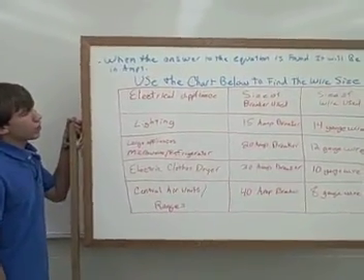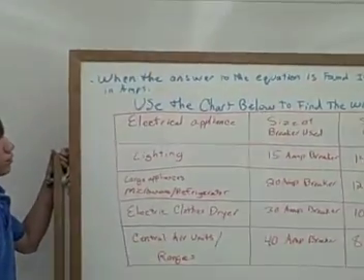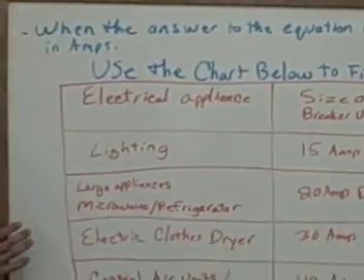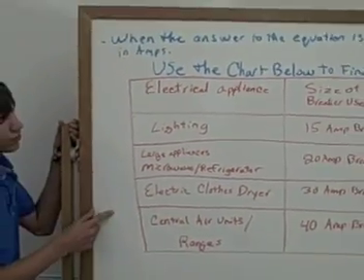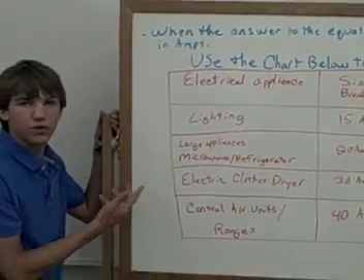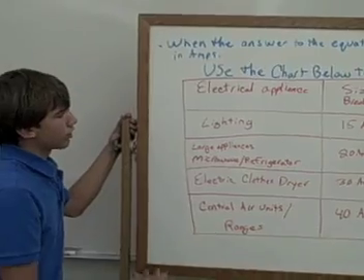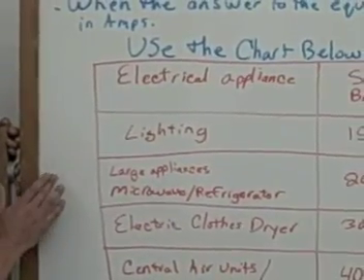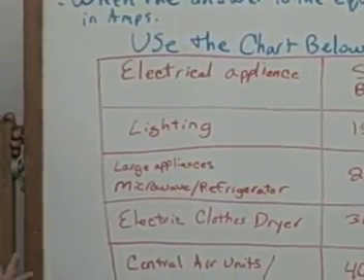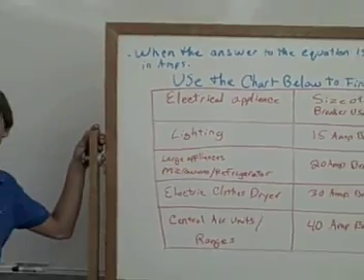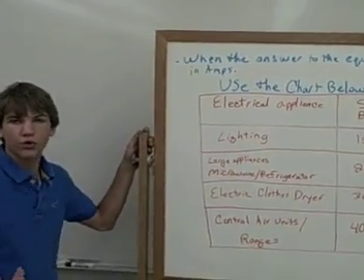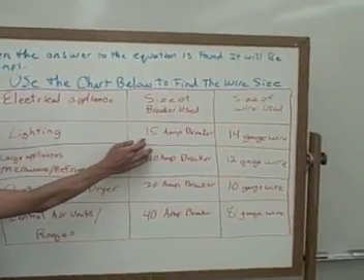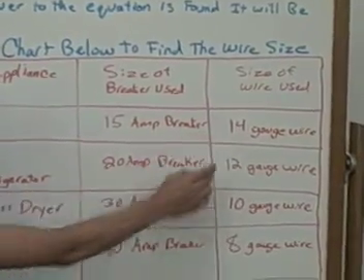When the answer to the equation is found, it will be in amps. You're going to use the chart below, which is found in the National Electric Code — basically the same thing I have here simplified down. So let's say you're doing a lighting circuit in your house. When you do that equation and find out that it draws only four or five amps, you would use a fifteen-amp breaker, then you would use fourteen-gauge wire.